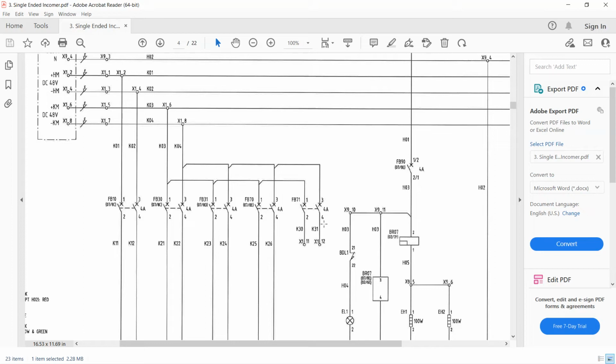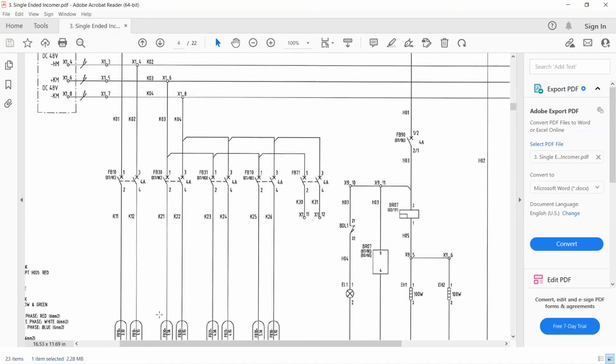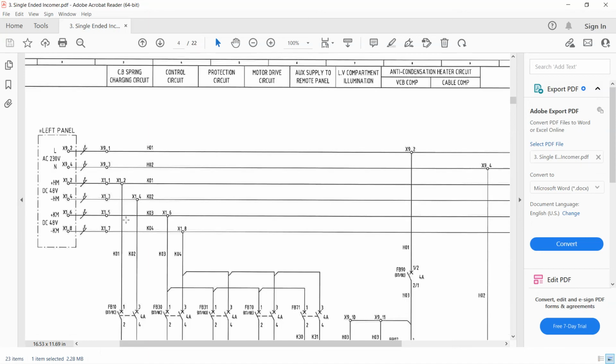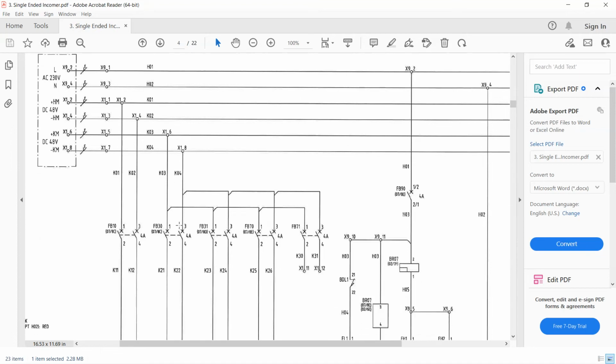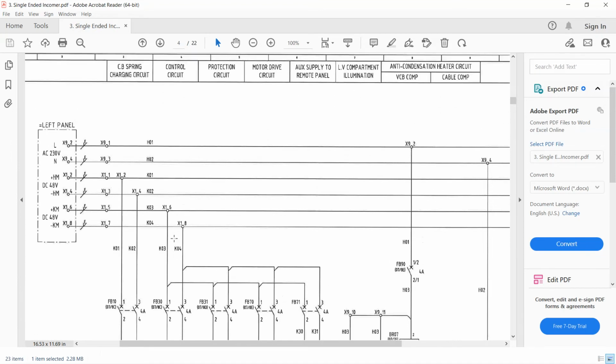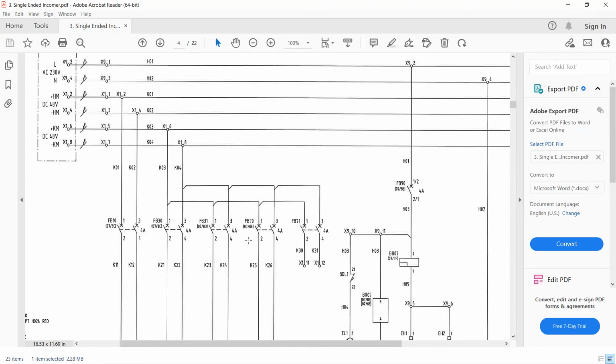In order for you to identify, like, I want to test the relay, but I want to connect my test leads, but the relay is live. How can I find which breaker is supplying it? If you look at this one here, there is a page number where this will be going, and you can see straight away that you have this group. On top, it means this line here supplies the circuit breaker spring charging. Some people test the breaker, so I'm going to switch this off because I'm going to touch the circuit. The control circuit is this one here. This control circuit means you have trip, open, and a specific supply for the protection relay. Now I know this is the breaker that I need to switch off. Also, all of this is designed for you to look at in one page.